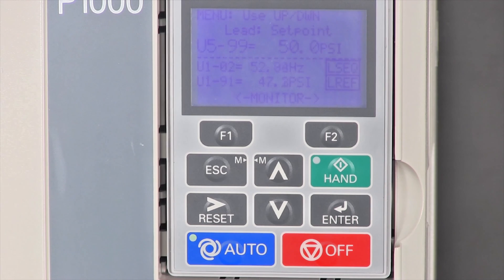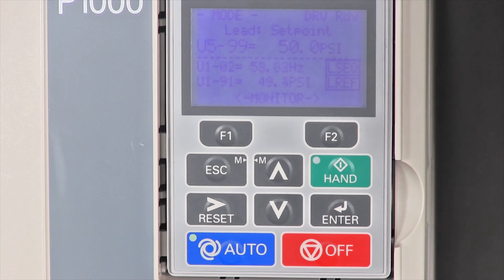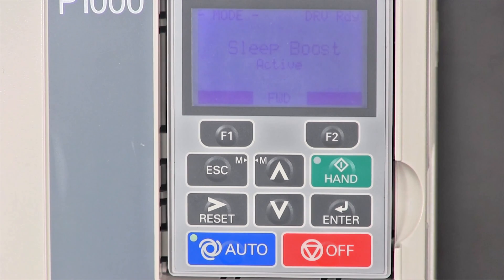If no water is used, the pump should go to sleep. However, right before it sleeps, it will boost the pressure an additional 5 PSI. You will see on the display, sleep boost.